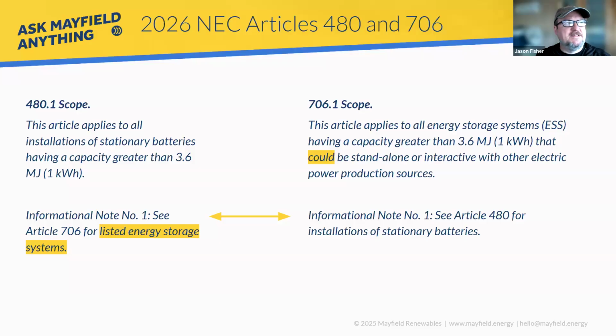There are a couple of things you might not see because they're deletions, relevant to this discussion. In both 480 and 706, and in the definitions of energy storage system and the previous definition of stationary standby battery, there was language around usage - like a battery that spends most of its time at float voltage, which is what used to be said for the stationary battery. And for energy storage, it was interconnected with the premises wiring and could be interactive or whatever. There was this attempt to say the use of these two pieces of equipment defines when you can install one or the other per the National Electrical Code.